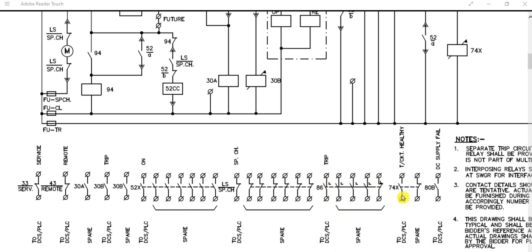74 is the trip circuit supervision relay. This relay checks the health of the trip circuit, and this indication is communicated to DCS or PLC. This is the DC supervision relay — 80B N.O. contact. This is a normally open contact used for the DC supply, and it is also going to DCS or PLC or the remote panel.